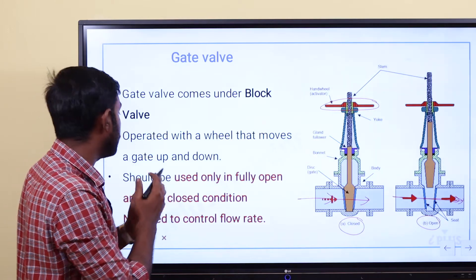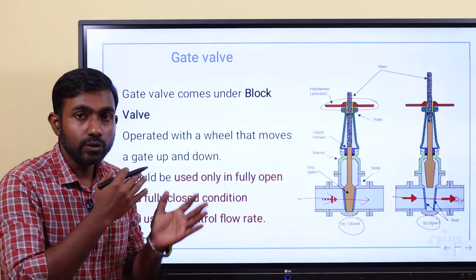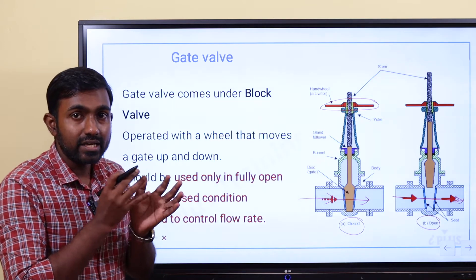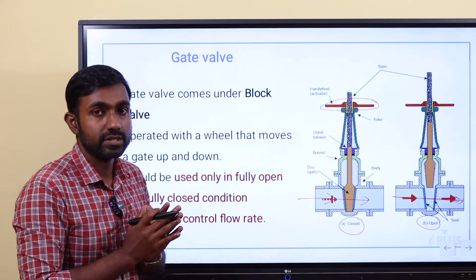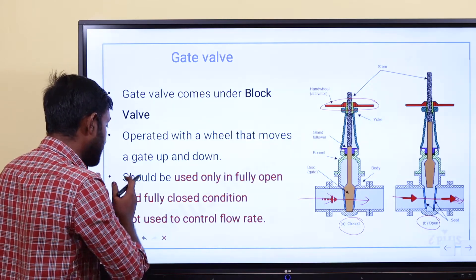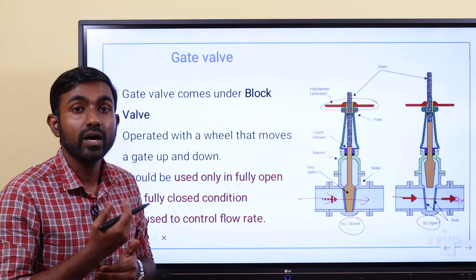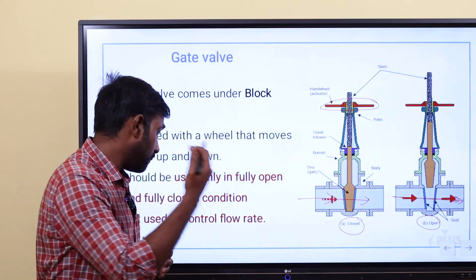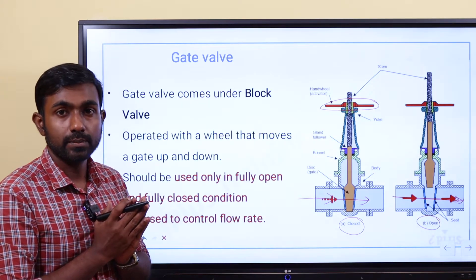The gate valve should be used only in a fully open and closed condition — that's very important. We can't regulate the water or change the flow discharge variation. It's either closed position or open position. The gate valve is not used to control flow rate. If you're looking to control flow rate, we can't use the gate valve directly.